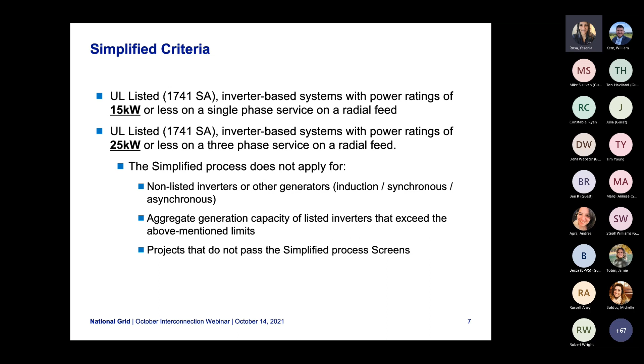Next slide please, I'm going to go through the simplified process with everyone. The simplified criteria consist of UL listed inverter-based systems with power ratings of 15 kW or less on a single phase service on a radial feed, or a UL listed inverter-based system with power ratings of 25 kW or less on a three-phase service on a radial feed. The simplified process does not apply for non-listed inverters or generators, aggregate generation capacity of listed inverters that exceed the above mentioned limits, or projects that do not pass the simplified process screens.